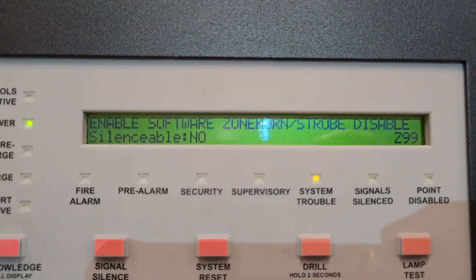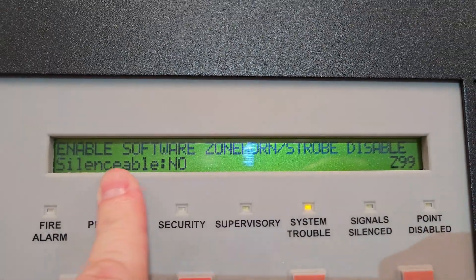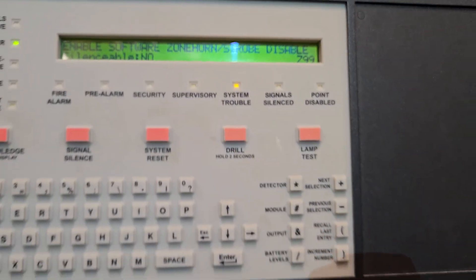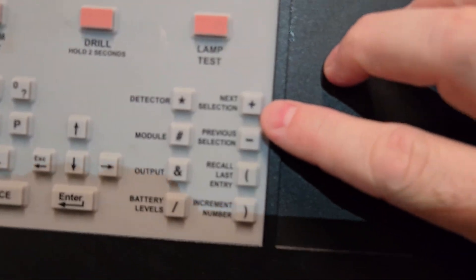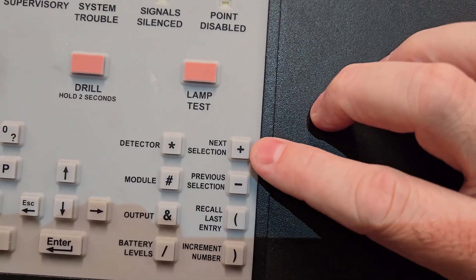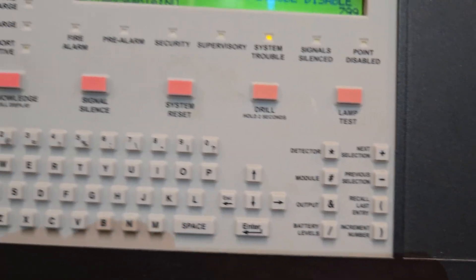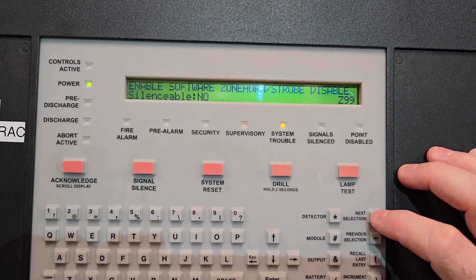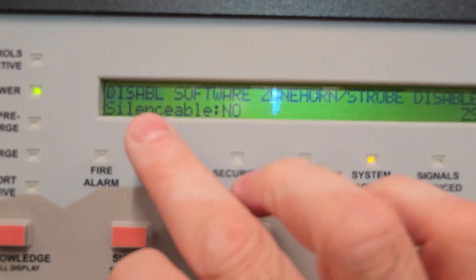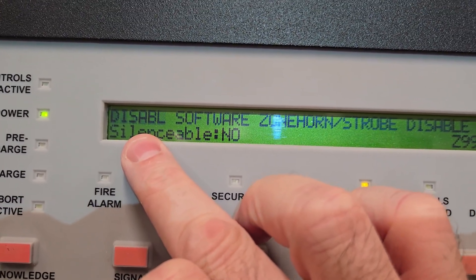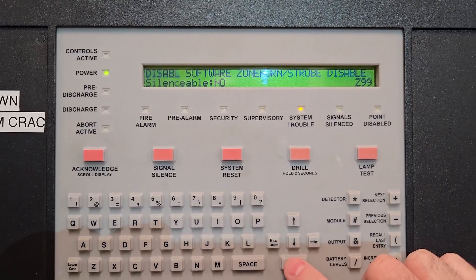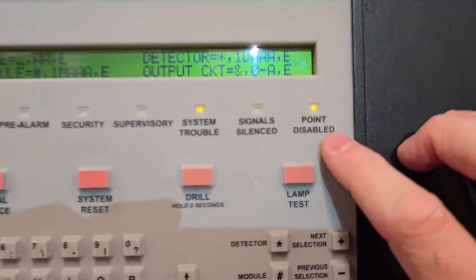I hit Enter to go to the next screen. It currently says 'enable — software zone 99 strobe — disable,' and it's flashing on 'enable.' To change it, I'm going to use the Next button. I hit the plus/next key and now it says 'disable' and it's flashing. So it changed from enable to disable. Now I hit the Enter button and it disables it. I now have the 'points disabled' light lit up on the panel.